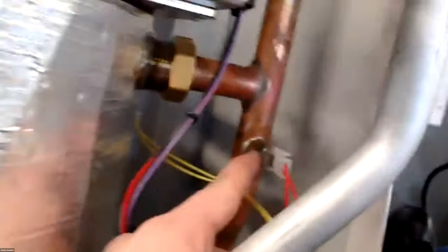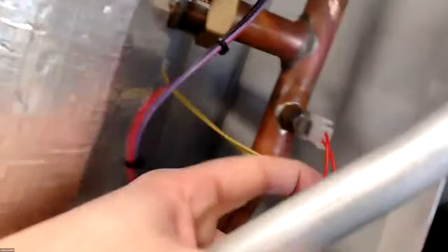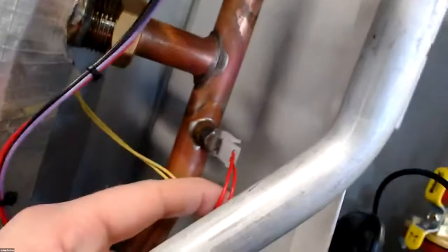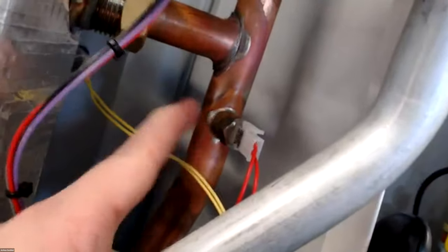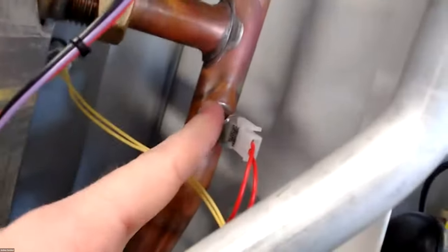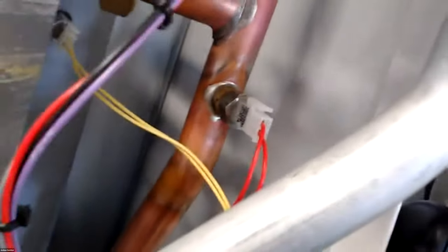Okay. Then working in the back here, we have our flue temperature sensor, which is this guy right here. Wire harness is in yellow. 12K sensor on this as well. Over here on our supply line coming down, we have another sensor. This is our supply sensor and we put it in red. Kind of makes sense. Again, 12K sensor, wet well, so if you do pull this sensor, make sure you drain down the boiler.